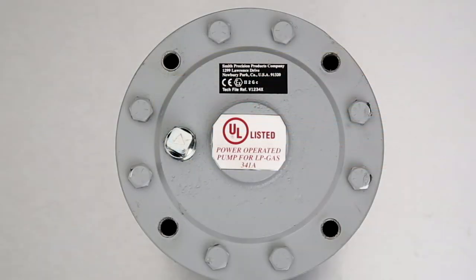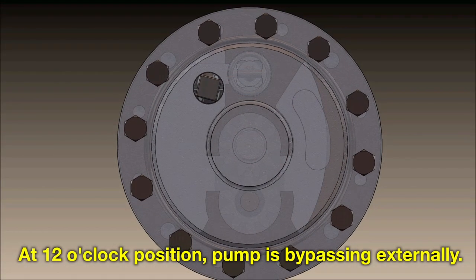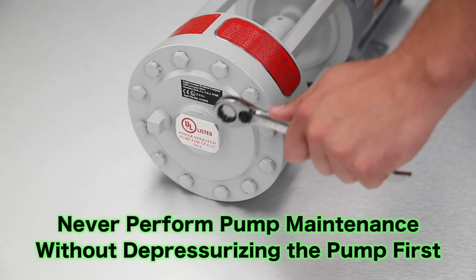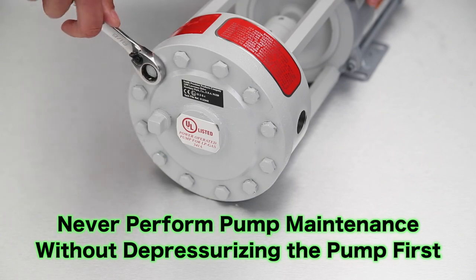For applications using the pump intermittently, the end user can use the internal bypass valve as an external bypass valve by changing the position of the cover plug to the 12 o'clock position. In order to do this, remove the 12 cap screws holding the cover onto the main housing using a 9/16 inch socket wrench.